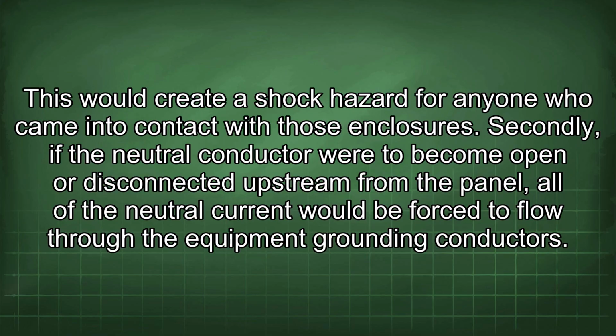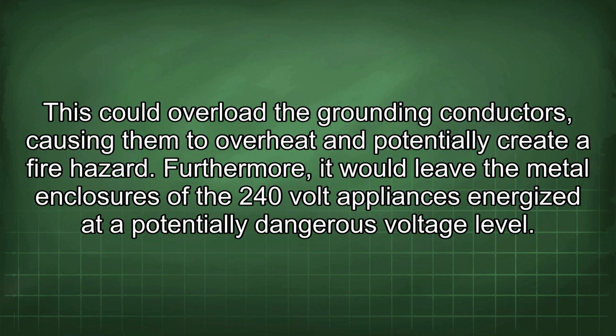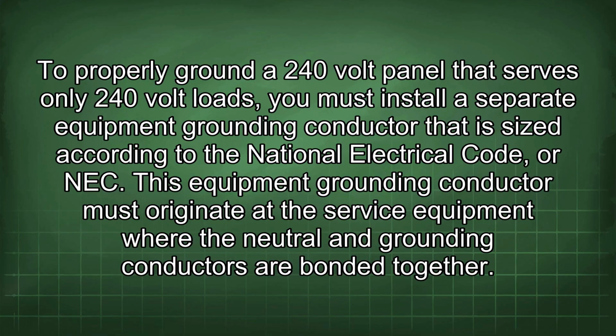Secondly, if the neutral conductor were to become open or disconnected upstream from the panel, all of the neutral current would be forced to flow through the equipment grounding conductors. This could overload the grounding conductors, causing them to overheat and potentially create a fire hazard. Furthermore, it would leave the metal enclosures of the 240-volt appliances energized at a potentially dangerous voltage level. To properly ground a 240-volt panel that serves only 240-volt loads, you must install a separate equipment grounding conductor that is sized according to the National Electrical Code, or NEC.